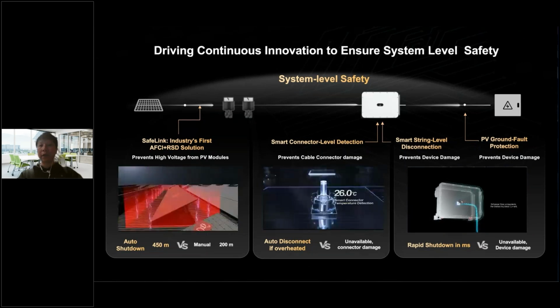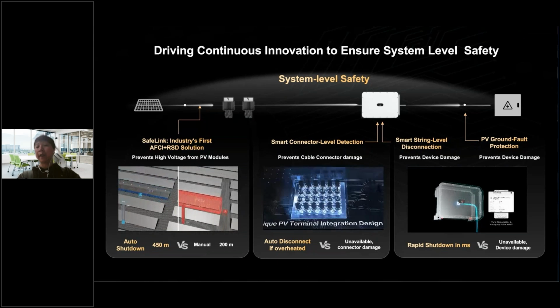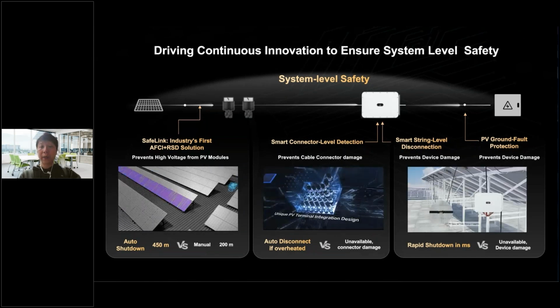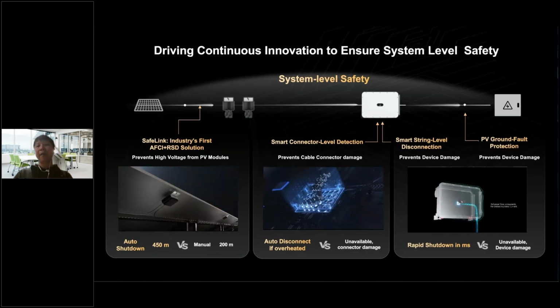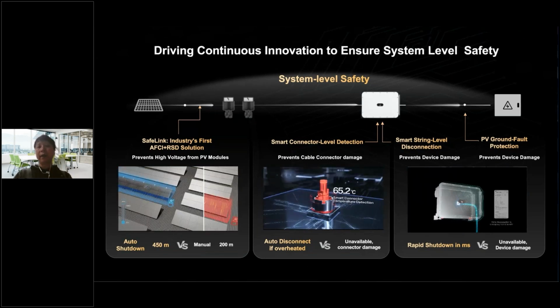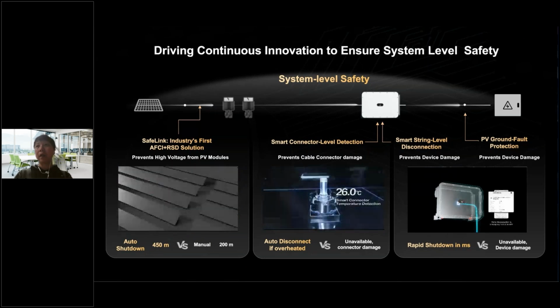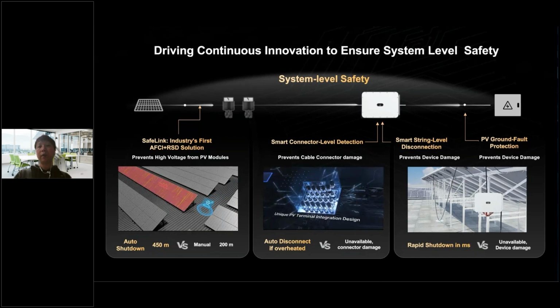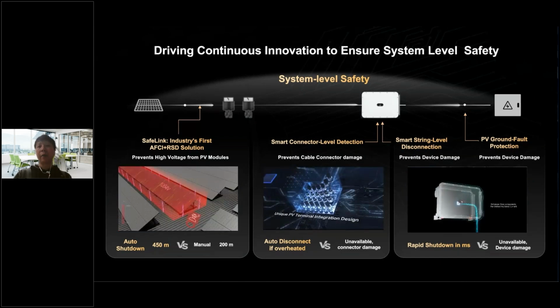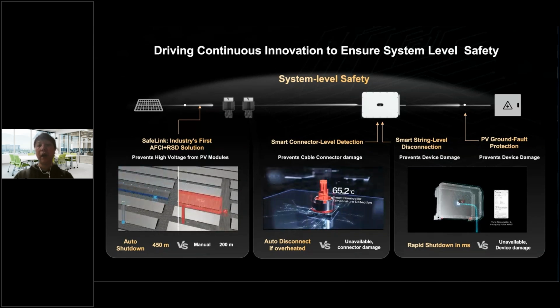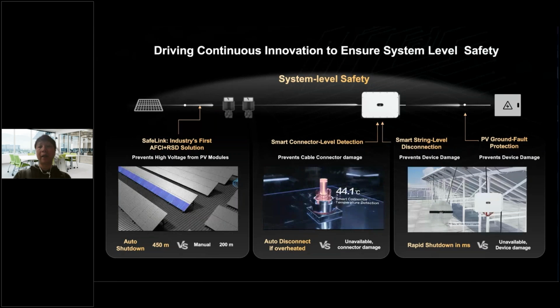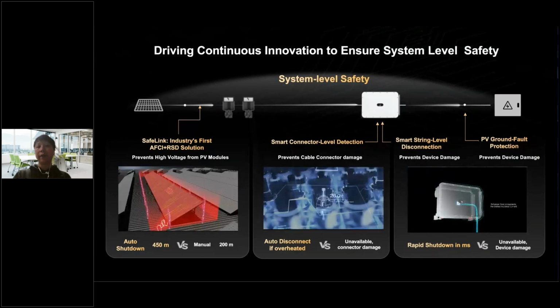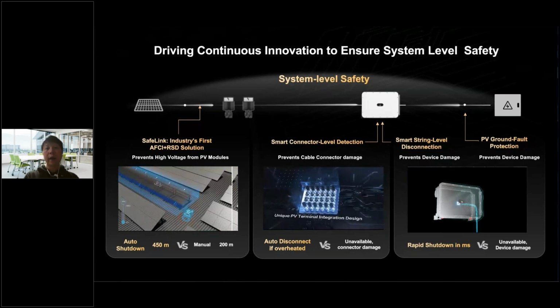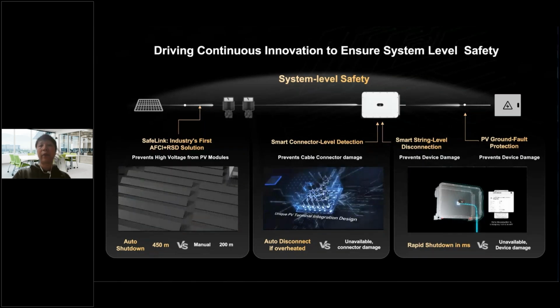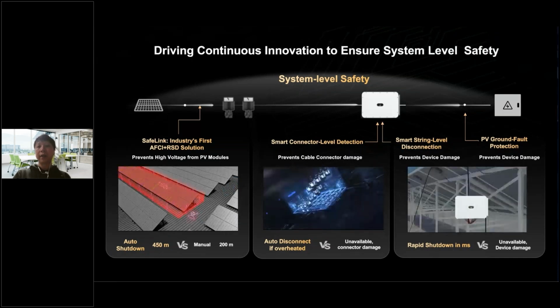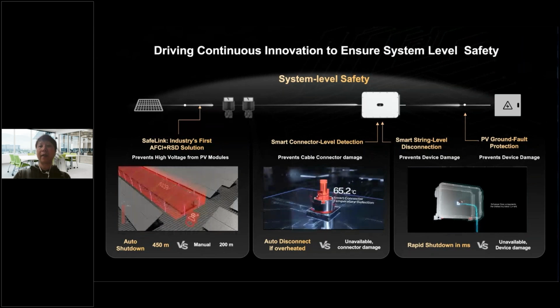And also the smart string level disconnector, which is actually the DC connectors on the inverters. For Huawei, we cooperate with our DC connector vendors and have customized these DC connectors. They can help prevent some reverse current or short circuit problems on the DC side, and prevent inverter damage from the DC side. We know most of the problems, about 60% to 70% of inverter safety problems, are caused on the DC side. But this SSLD can help protect our inverters from reverse current or reverse high voltage problems on the DC side. So this is also unique to Huawei, and we have a patent on this SSLD feature.